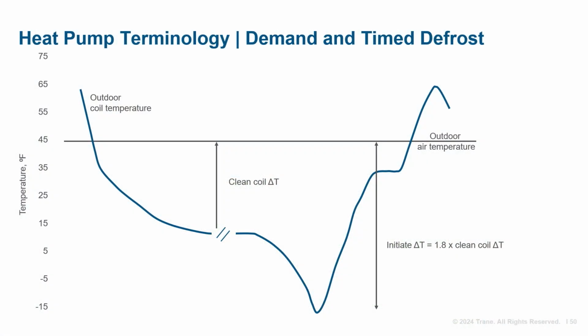In the next slide, we'll discuss the two common defrost methods and review how the defrost sequence takes place. There are two common methods used for outdoor coil defrosting: demand and timed defrost. First, we will review the demand method. Demand defrost monitors the ambient conditions, along with the mechanical system temperatures, before initiating a defrost sequence. It activates the defrost cycle only when needed based on the condition of the coil, saving energy by minimizing unnecessary defrost cycles. This illustration indicates that two conditions must be met before any defrost cycle can take place.